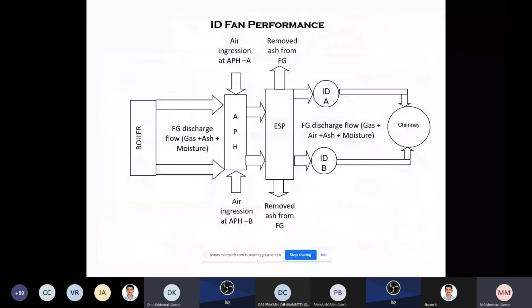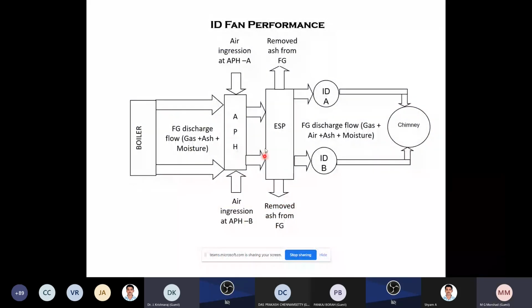Likewise, the ID fan. From the boiler, the two paths will be there. It is coming from the air preheater. Here, if a leak is there, the air will go inside, sucked in, because it is a vacuum. Then the ESP. From the ESP, you will remove the ash. After that it is going to the ID fans, IDA and IDB. Then it is going to the chimney.